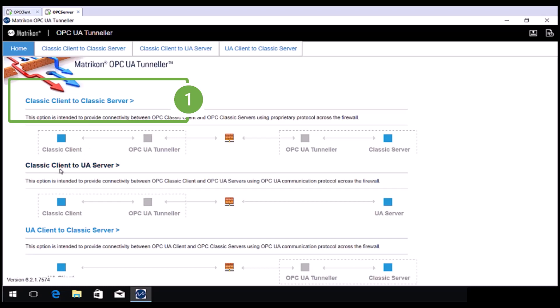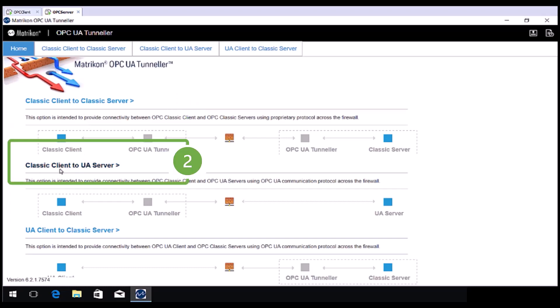The next mode is Classic Client to UA Server. You would normally use this mode when you are trying to connect an OPC Client that supports a Classic OPC specification to an OPC Server that supports the UA specification.